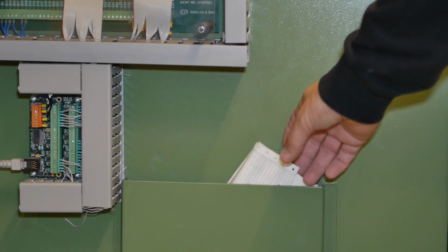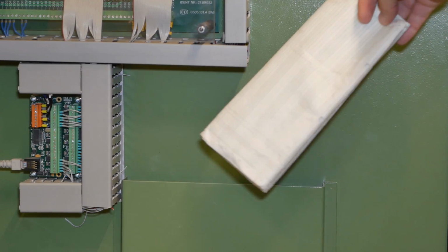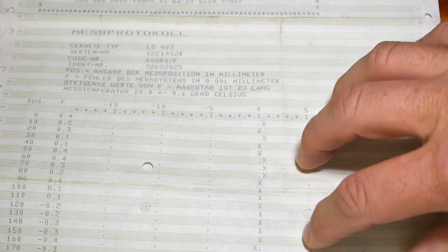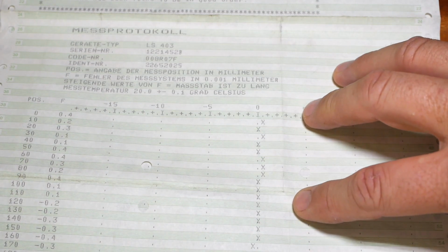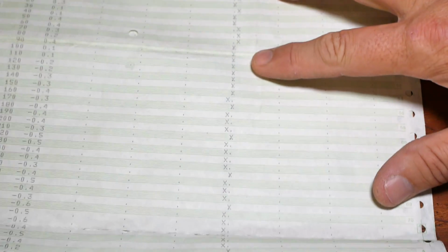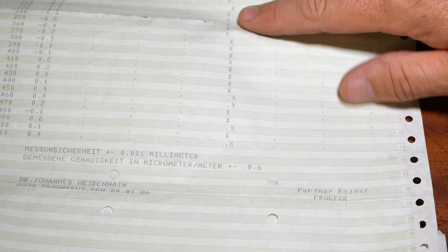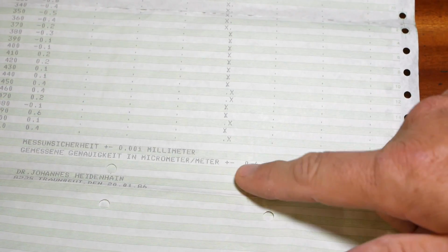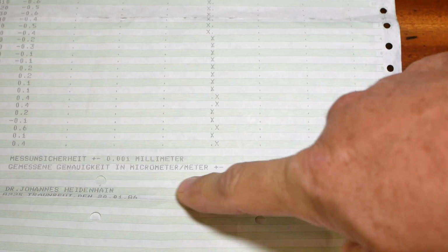Fun fact: Heidenhain included the original calibration protocols for the linear encoders with the machine. If we look at the certificate of inspection for this scale, we can see the maximum deviation over its half-meter measuring length is 0.6 of a micron.